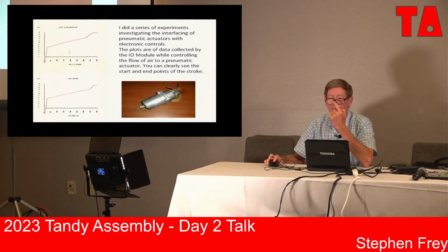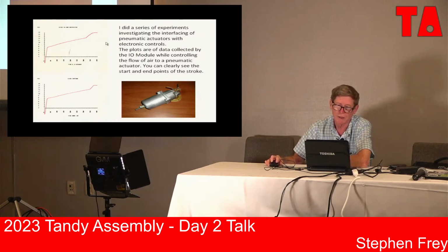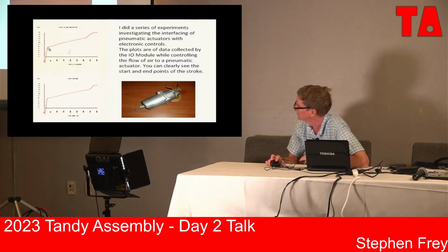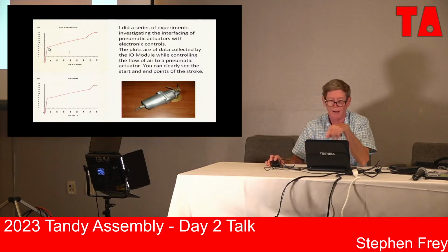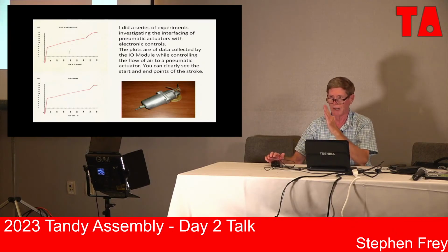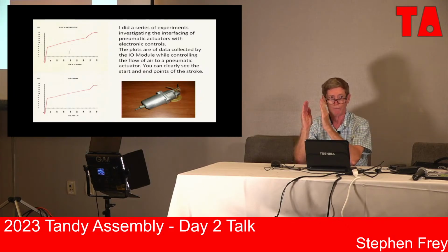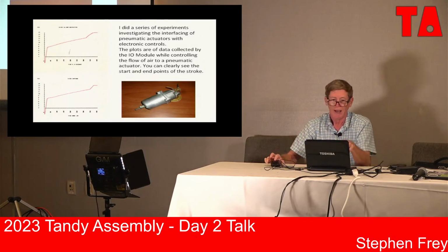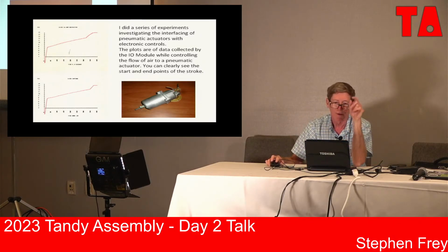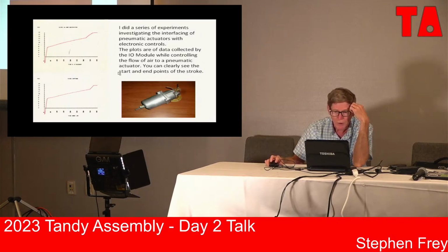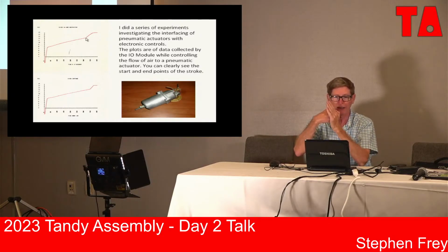This is a plot showing the pressures, and the interesting thing it demonstrates is these little elbows here when it first comes up. Can you see my cursor? It comes up at a fairly straight, steep line, because at that point it's a small volume. Then when it gets to that break point, that's when it actually starts to stroke, and you see this long line going up. Then here's where it gets to the point where it stops moving again, and you can see the definite break in the characteristics that lets you know.